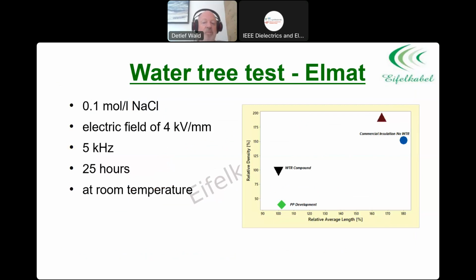We made more comparisons there. We made a water tree test at ELMAT, the University of Bucharest. Here you can see that the polypropylene compound had the same water tree retardancy as a commercial water tree retardant compound. Once again, the density and the relative length were put at 100% in relation, and the PP has fewer water trees, that means less contamination, and only a slightly higher water rejection rate.